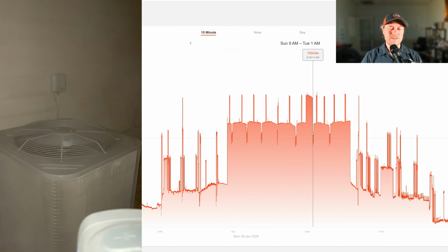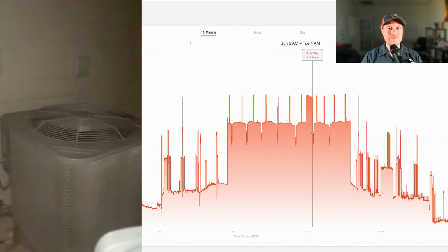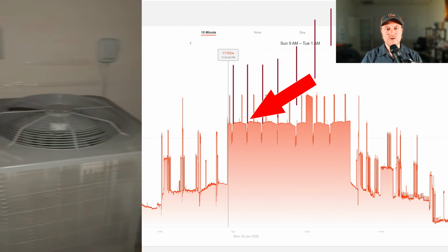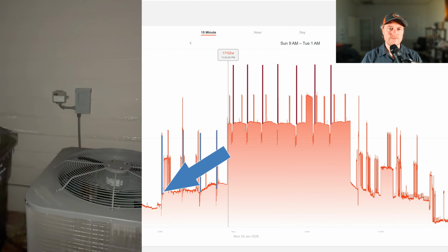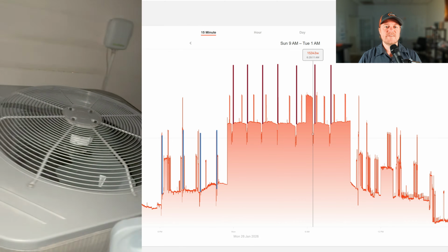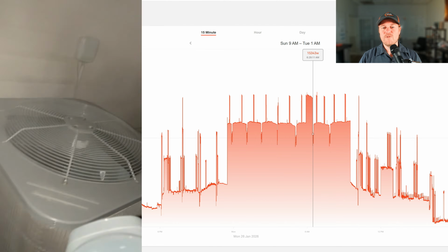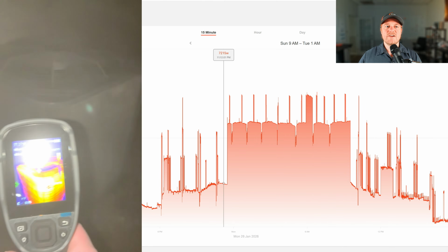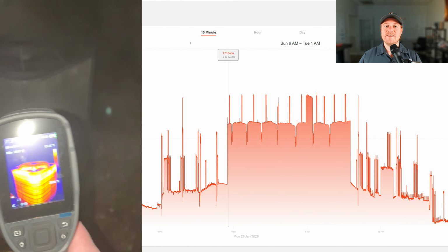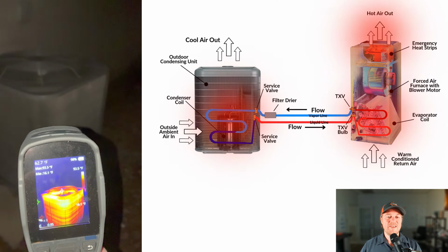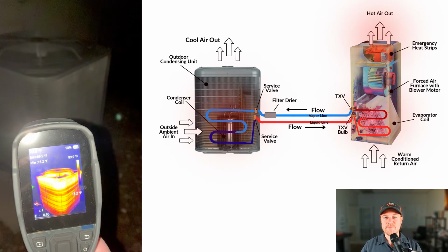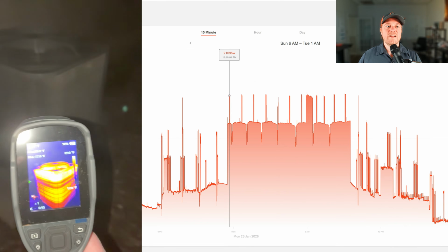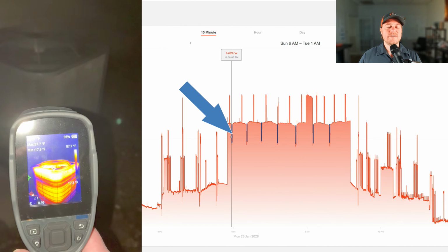And you might be asking, if the system's in defrost mode using the heat kits, why don't we see a similar spike here like we do over here when it's in defrost mode? So what's happening here is I have the thermostat set at 68 degrees, and the heat pump itself can't keep up. So what it's doing right here is running the heat pump and the heat kit at the same time. So both the heat pump and the heat kit are heating at the same time to kind of supercharge the heat. And here these little dips are when the system is going into defrost mode.